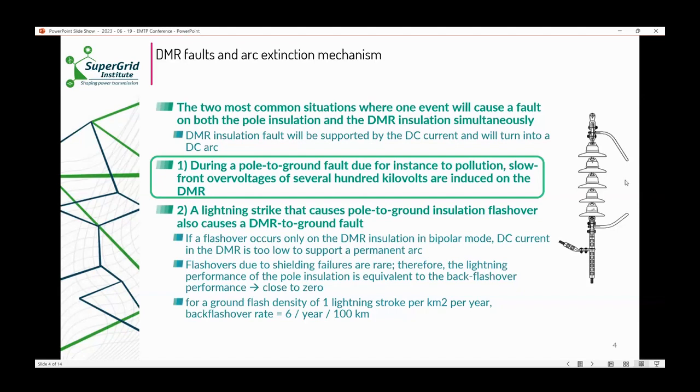What faults can cause voltage or outage of both pole insulation and DMR insulation simultaneously? If this happens, the DMR insulation fault will be supported by the DC current and will turn into a DC arc, which we don't want. Two of these events: one is during pole to ground fault due to pollution on a positive pole, for example. Slow front overvoltages of several hundred kilovolts are induced on the DMR. If it's insulated for medium voltage, we're going to have a flashover either on the surface of the insulators or between the two arcing horns. You can see a typical DMR insulator on the right hand side. Second event: lightning strikes that cause a pole to ground insulation flashover and also cause a DMR to ground fault. If a flashover occurs only in the DMR insulation in bipolar mode, DC current in DMR is too low to support the permanent arc, so it will extinguish itself. The lightning performance of the pole insulation is equivalent to back flashover performance. We calculated in this paper for poles it's close to zero. For an example of a ground flash density of one lightning stroke per kilometer square per year, back flashover rate of DMR is six per year per 100 kilometers. In this paper, we decided to concentrate on the slow front overvoltages due to pole to ground faults on positive or negative pole.